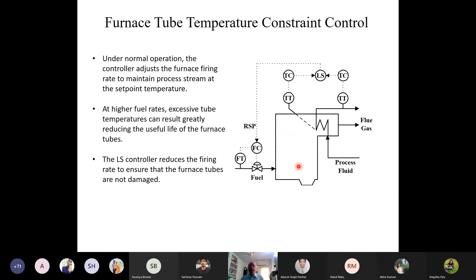So we use a low selector over here, and we tune the controller output in such a fashion that when this temperature increases, this temperature controller will override the normal control strategy of the TC-FC cascade. Under normal operation, the controller adjusts the furnace firing rate to maintain the process stream at the set point temperature, and at higher fuel rates, excessive tube temperature can result, greatly reducing the useful life of the furnace tubes, because as the process fluid increases, you will have a higher fuel rate. The low selector controller reduces the firing rate, which ensures that the furnace tubes are not damaged. So when the skin temperature increases, this will be the control loop. So this is the furnace tube temperature constraint control.